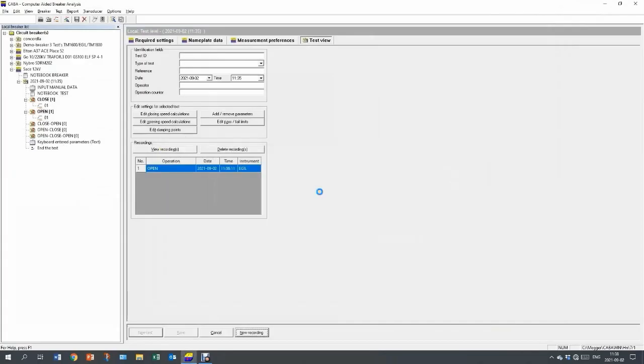And now I want to do more measurements. If this was in the real world, I would actually do 3 of each kind. But this will be the same procedure, so I close here. But what you need to know is that in this situation, I have actually only done 1 proper recording, because my first measurement was a calibration. So this one is actually not considered a real motion measurement.